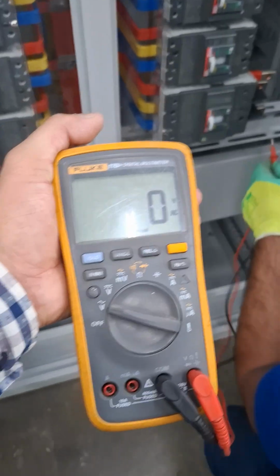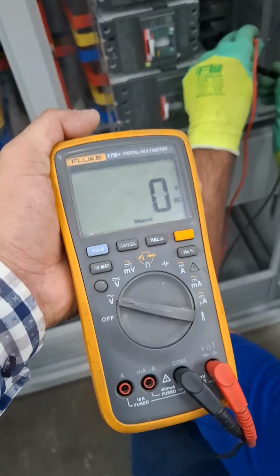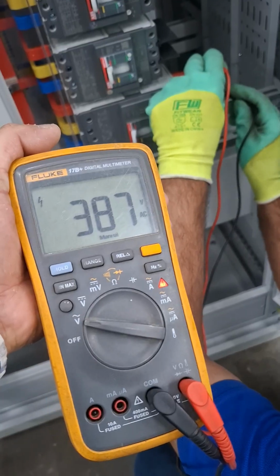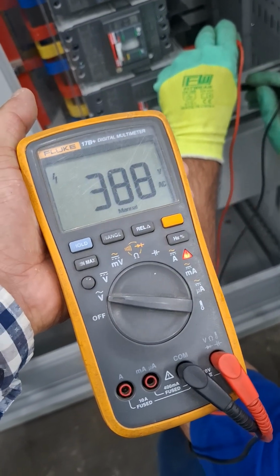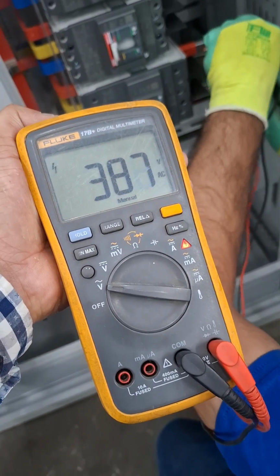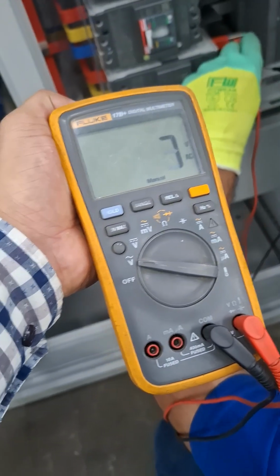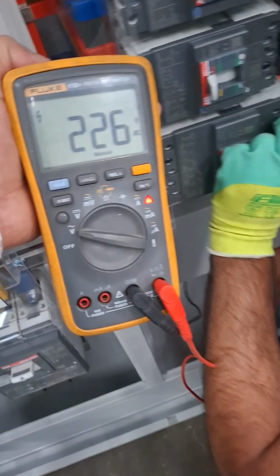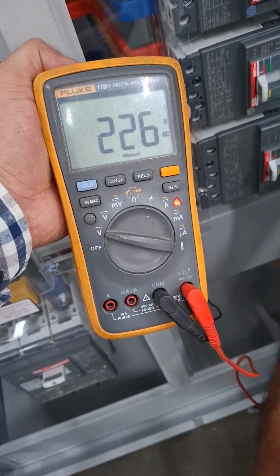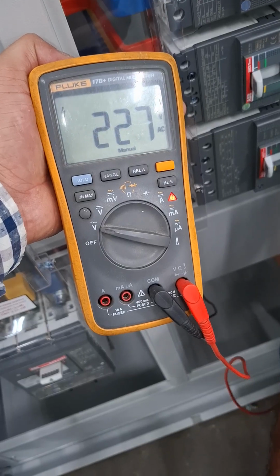now he is checking the outgoing voltage. Line 1 with line 2, line 1 with line 3, line 2 with line 3. Okay. Line 1 with neutral. Okay. Line 2 with neutral, line 3 with neutral.